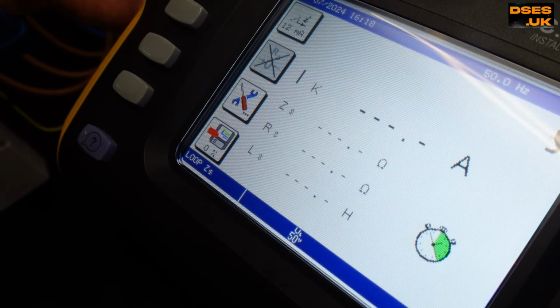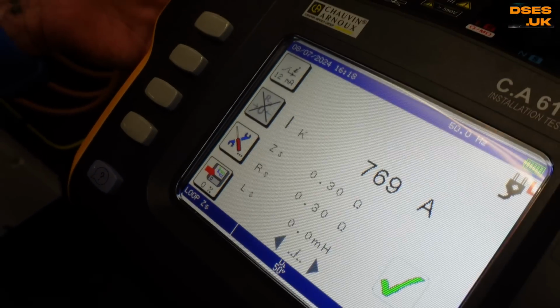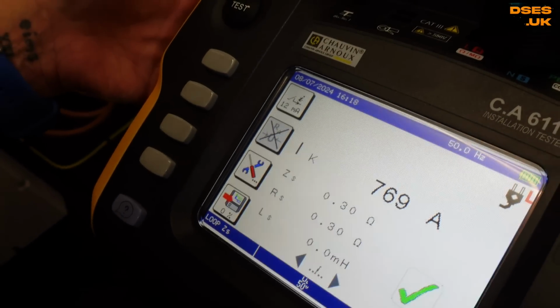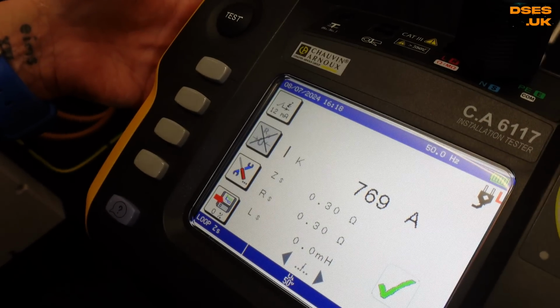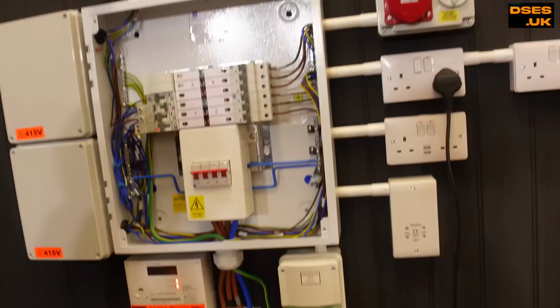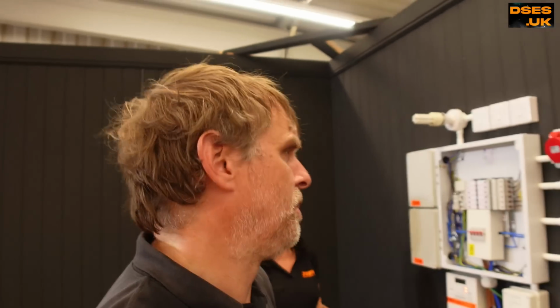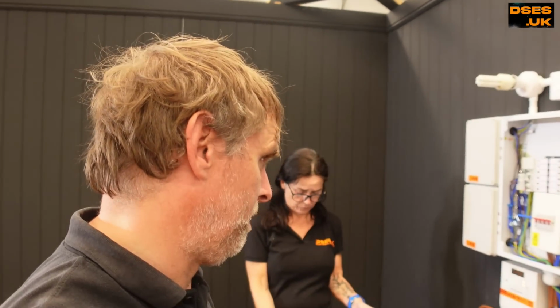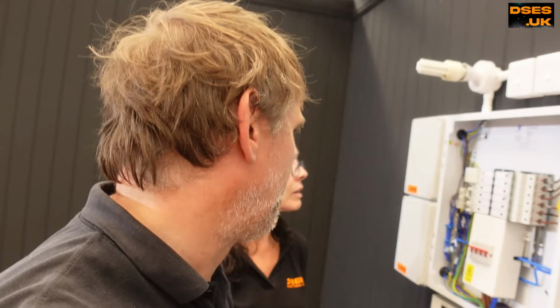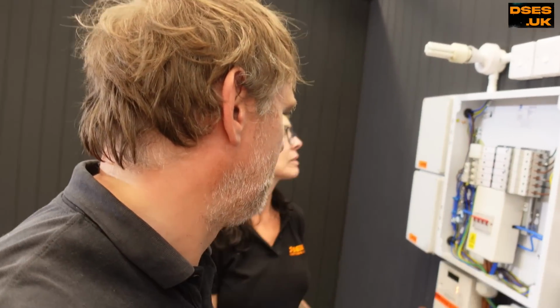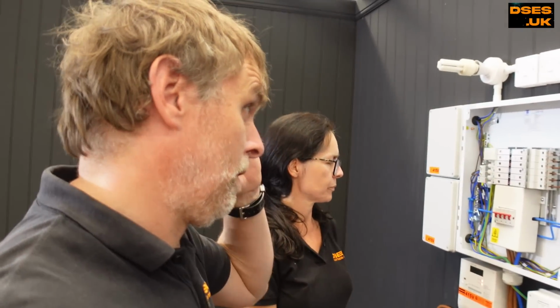The CA6117 says it's 0.30 ohms with a fault current of 769 amps. So if we were to join line to earth in here, potentially up to 769 amps would flow. Of course it wouldn't, because we have our protective devices in there. That one's off at the moment.